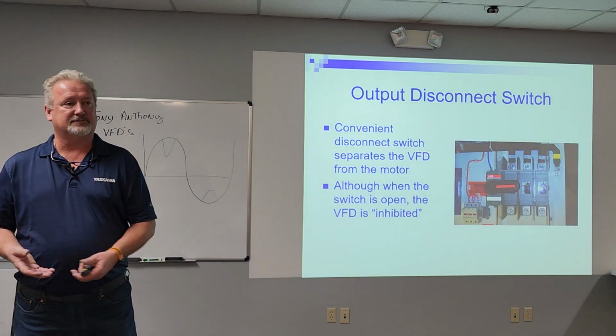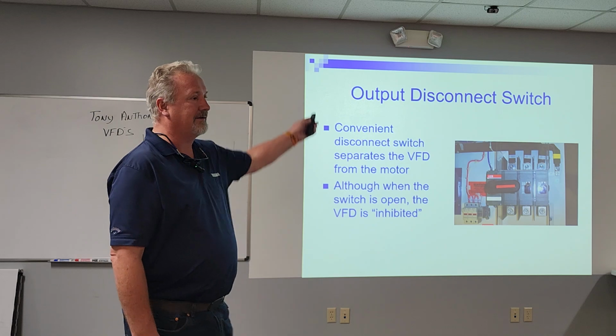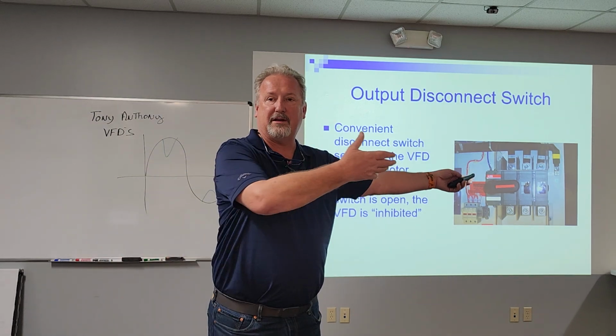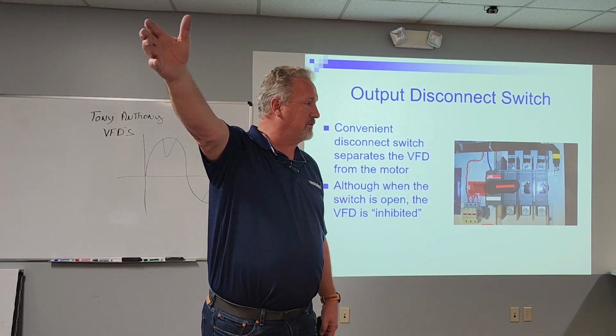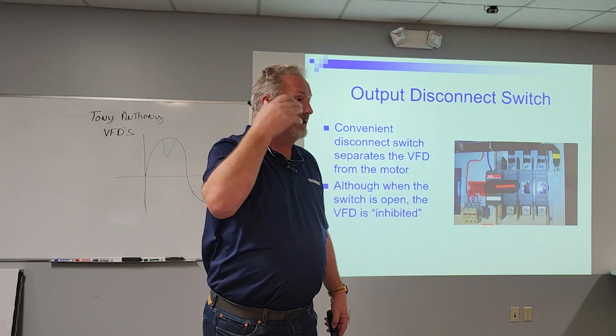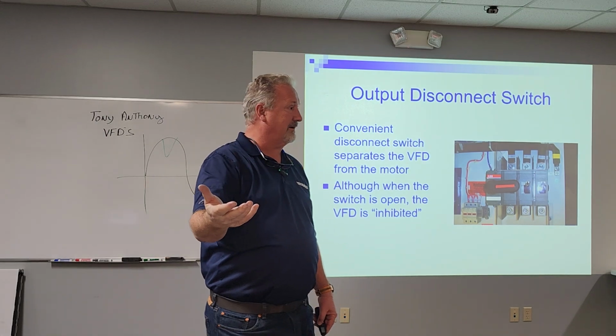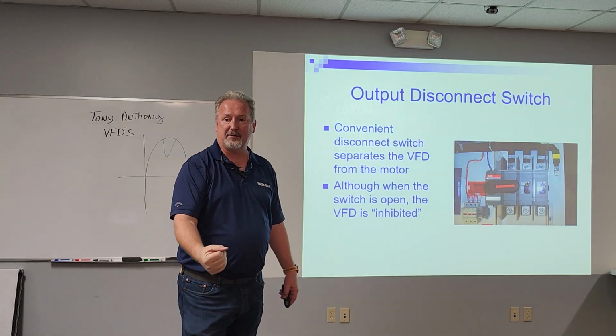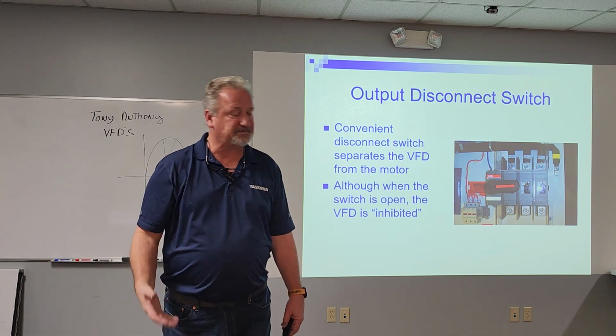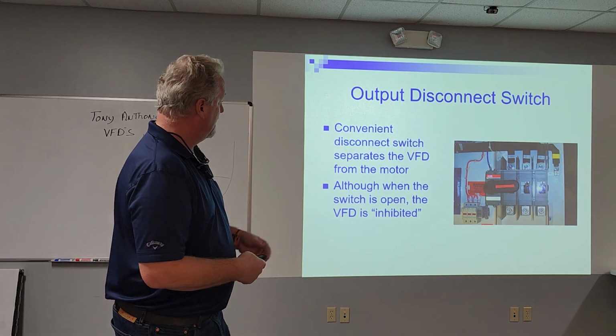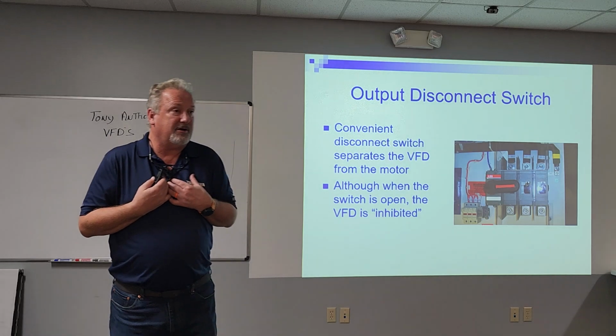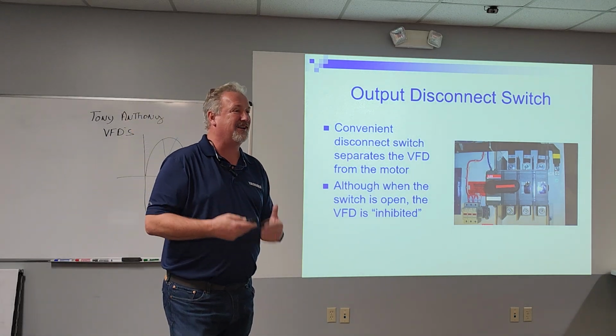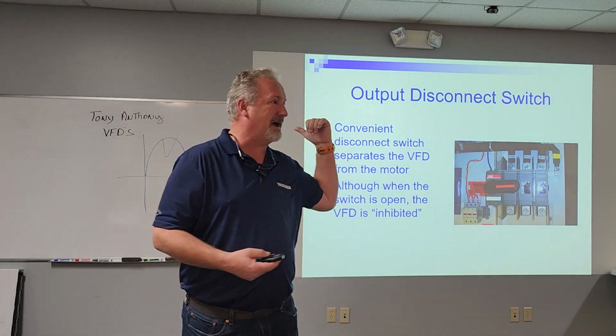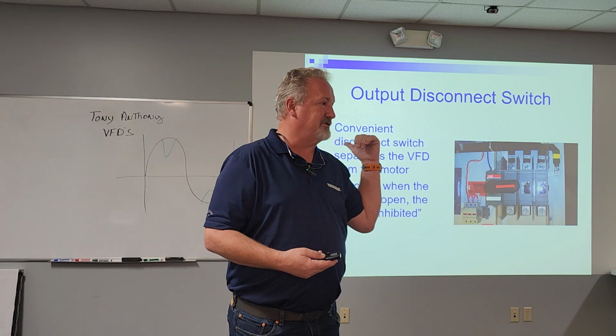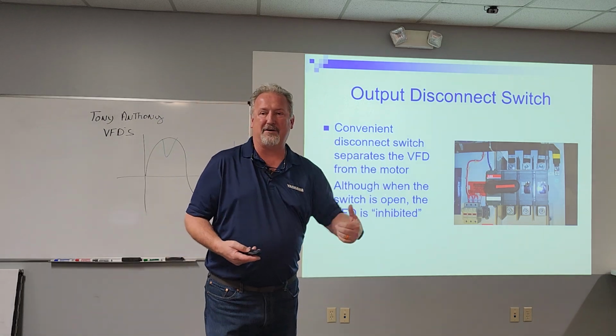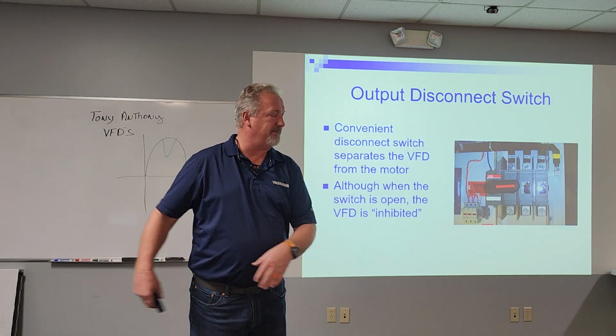Output disconnect, commonly called a line of sight disconnect. If your drive's in a control room and the motor's out on the floor somewhere or up on the rooftop, you've got to have what's called a line of sight disconnect. You've got to have a means to disconnect that motor if you have to work on it. And there's nothing wrong with that. One thing we wish you would always do, at a minimum, is make sure your lockout tagout procedure tags out the drive as well. Because you can go out there and trip that drive off, or open that disconnect and take that motor off the line.